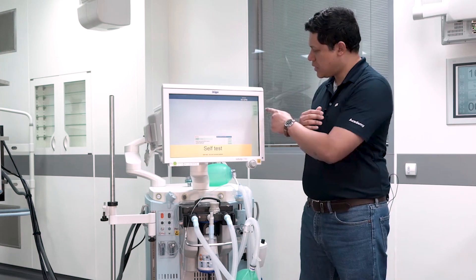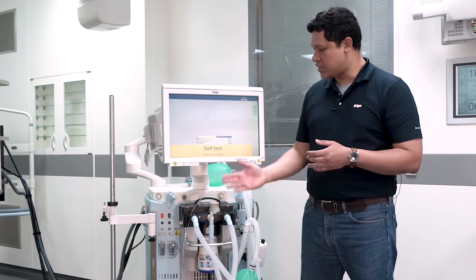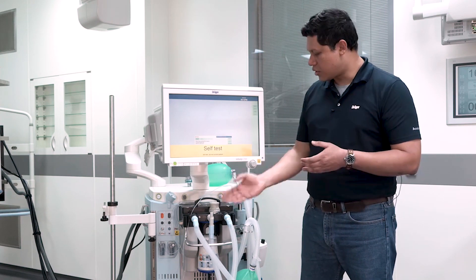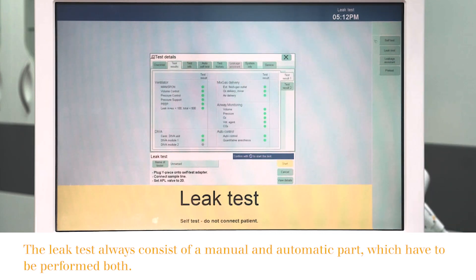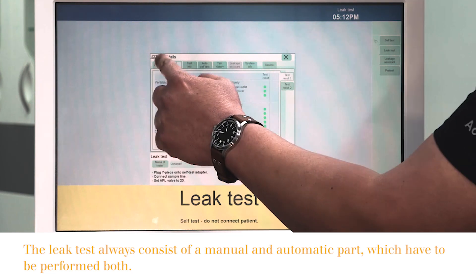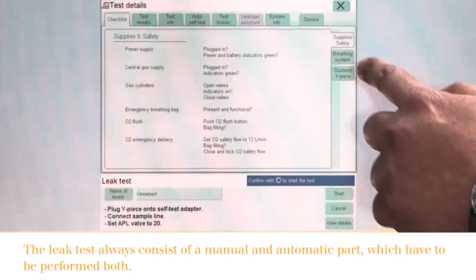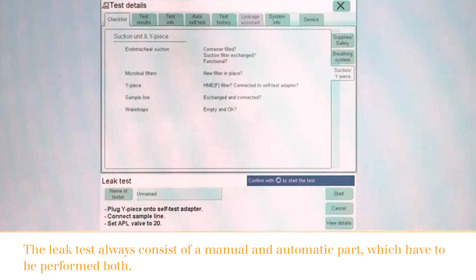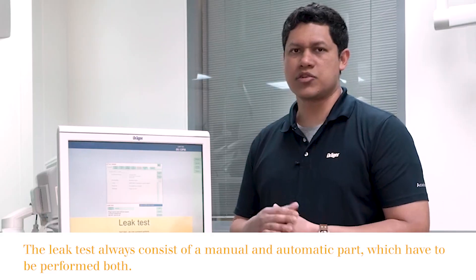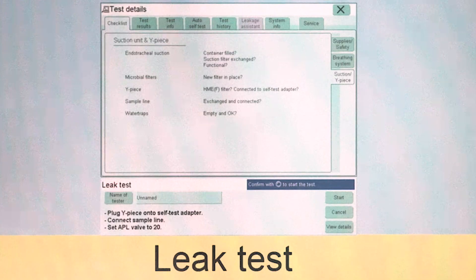The second test that you can perform is the leak test. This one should be performed between patients once you have exchanged the breathing hose system, the soda lime canister, or the water trap. Here you press on the leak test button and you will be displayed with the same checklist we just reviewed for the self-test — supply and safety components, breathing system components, and suction and Y-piece systems. Once you have gone through the complete checklist, you just press start to continue with the leakage test.